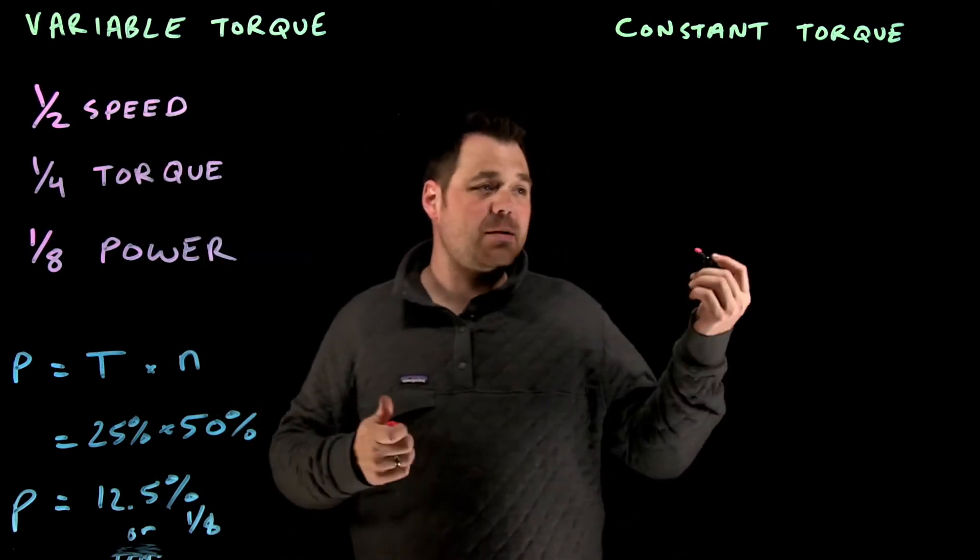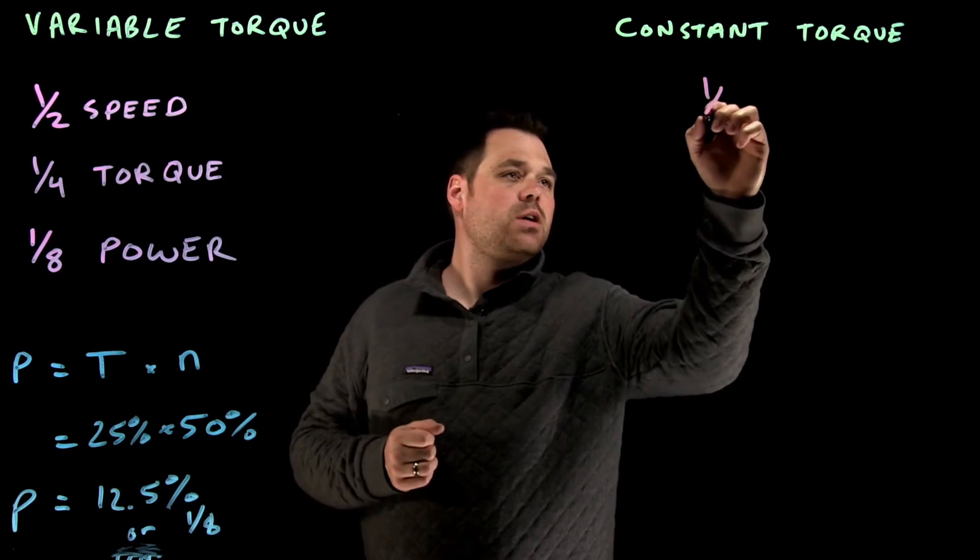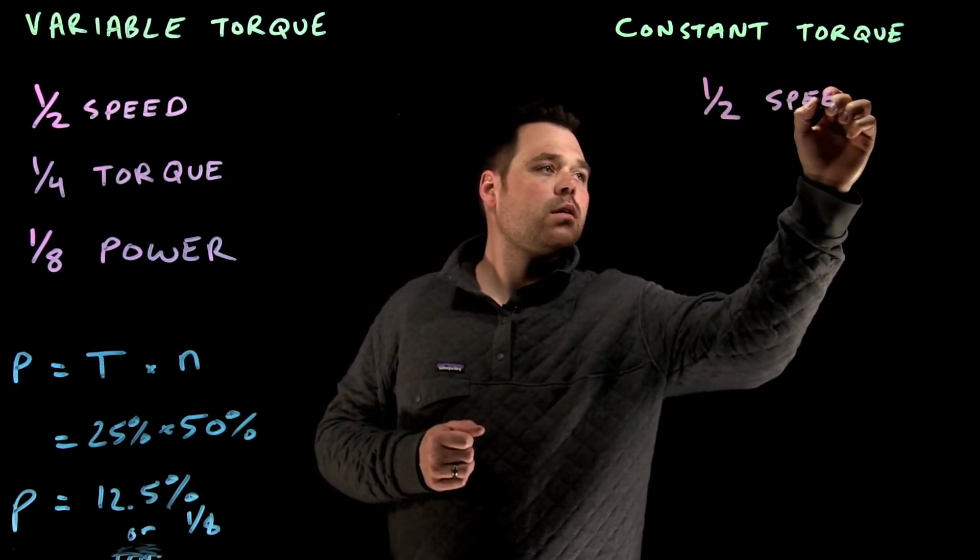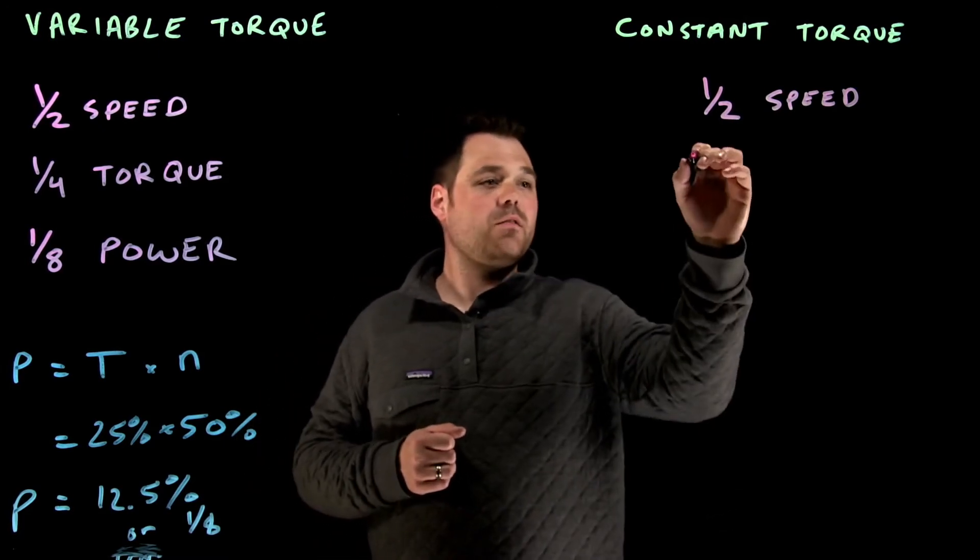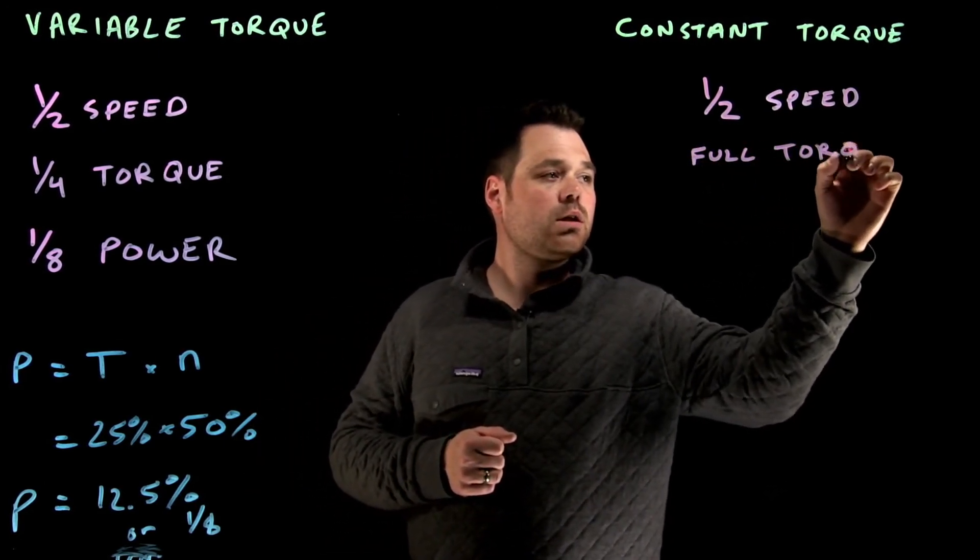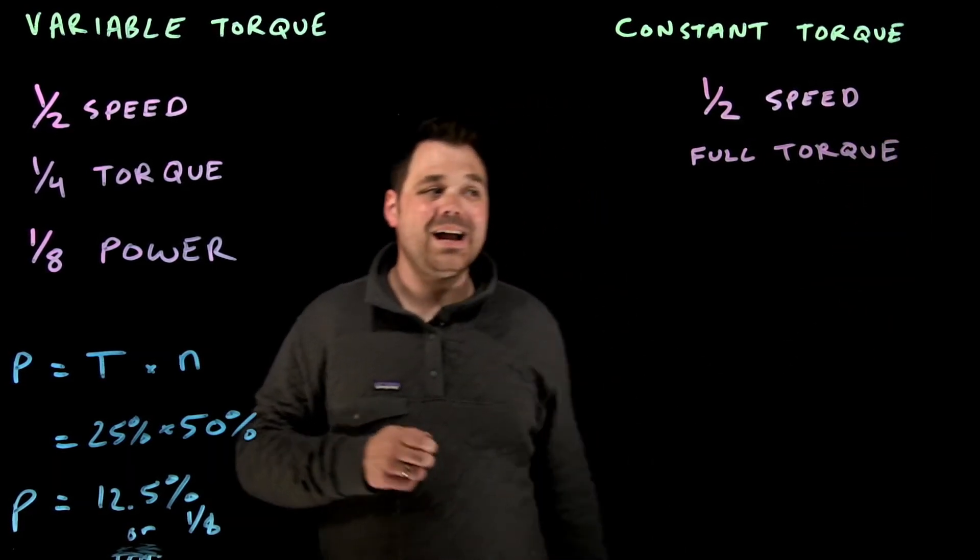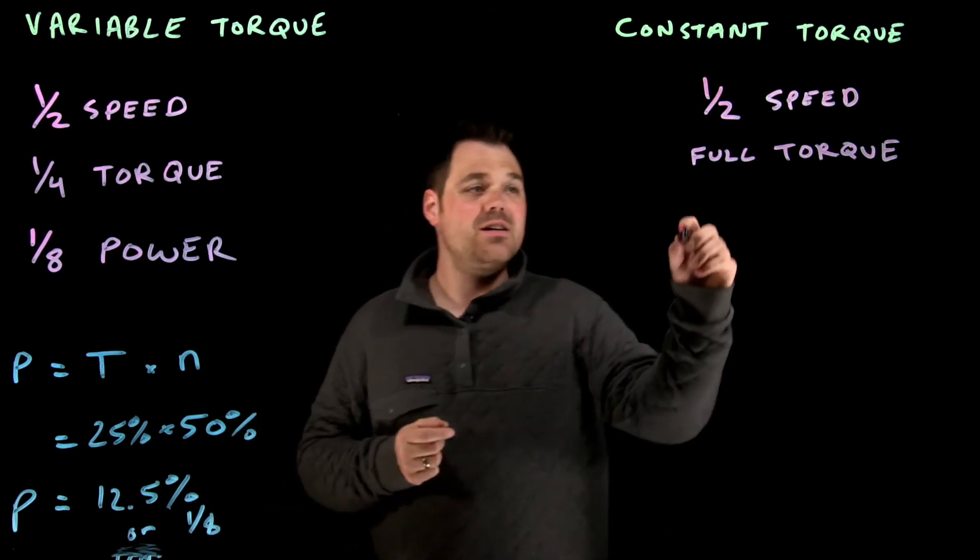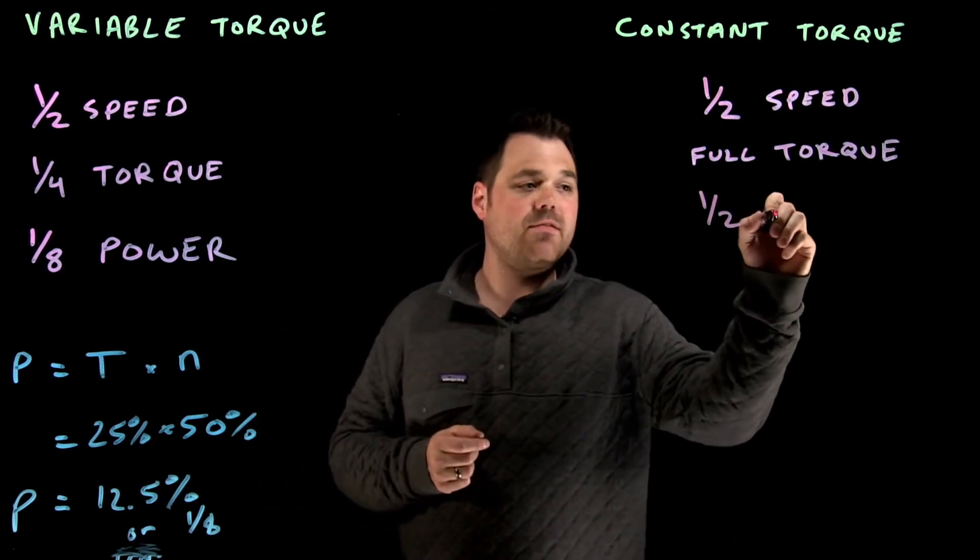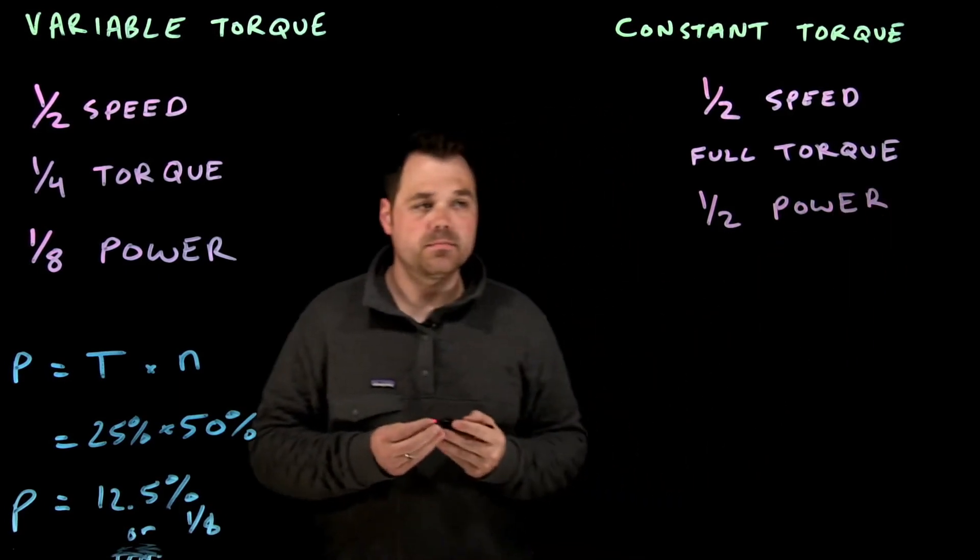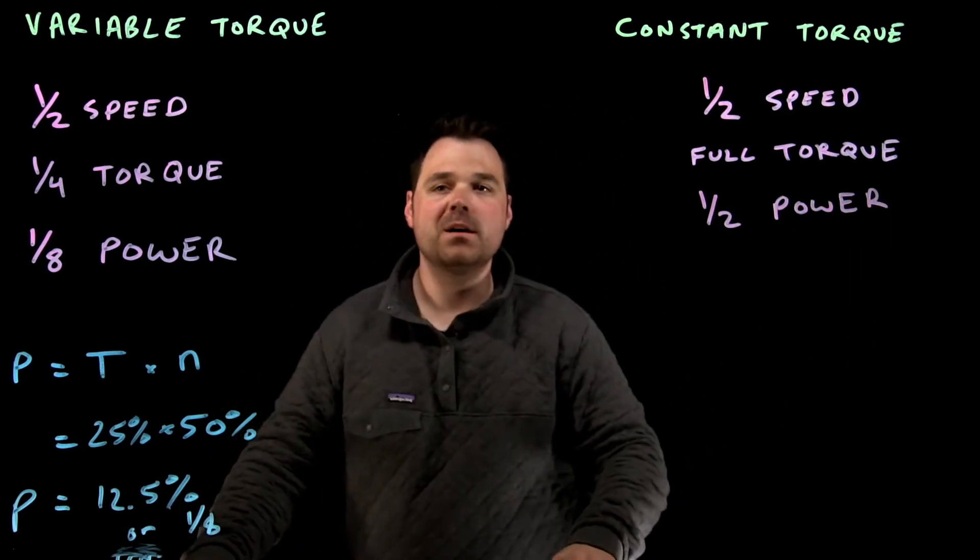Using our half speed as an example, if I'm talking constant torque, if I was at half speed, I would still require full torque. But, I actually am still going to see a little bit of energy savings in that I would only require half the power. Let's talk about how that works out.